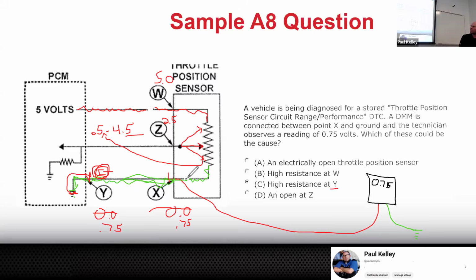What if we were to have an open right here? What if we fix that top open and we had an open down here? You'd have 5 volts, you'd have 5 volts. 5 volts would come all the way to here, right? So what voltage, if we have 5 volts going all the way to here, that means you're going to have 5 volts going all the way to here. That means your sensor is not going to read 0.5 to 4.5. What's it going to read? You've also got a code for that. So that would be a high voltage, or a 0.0 is going to be a low voltage.